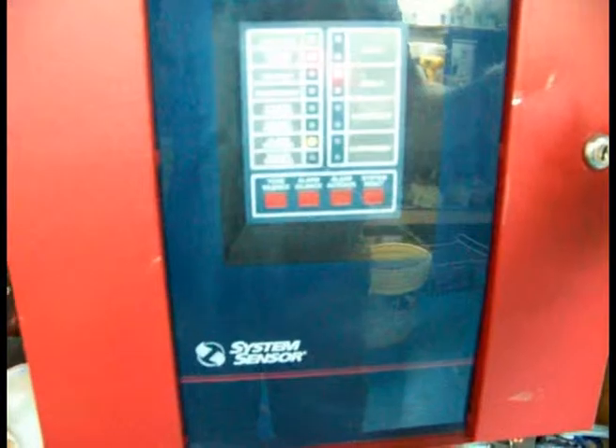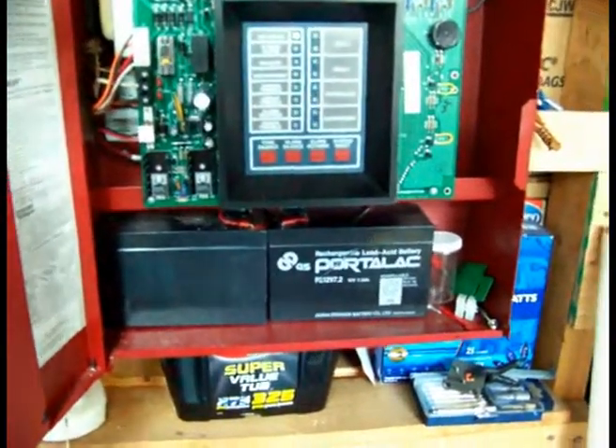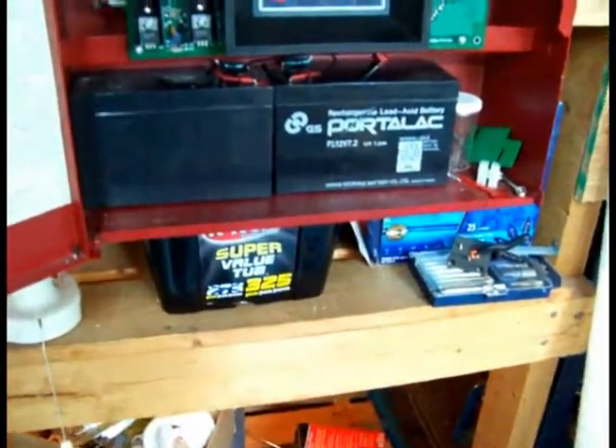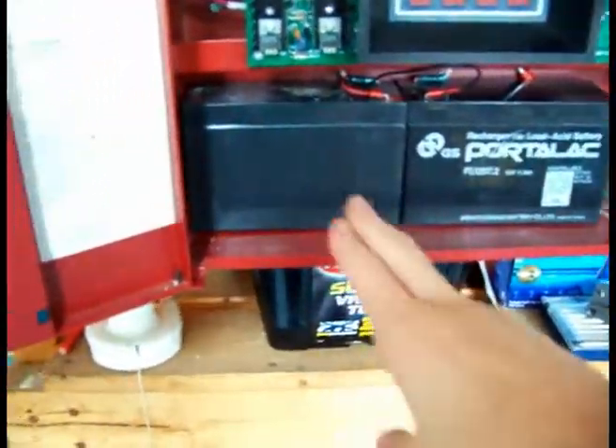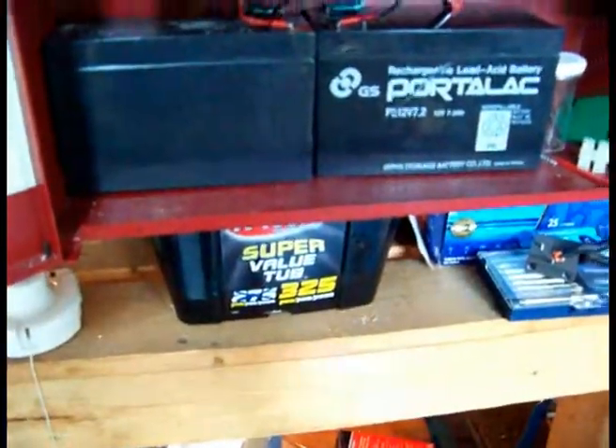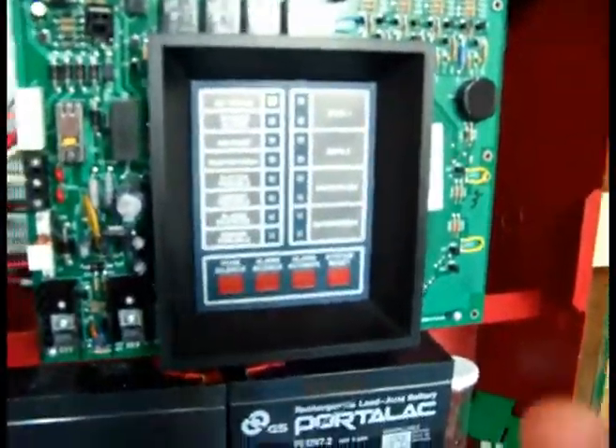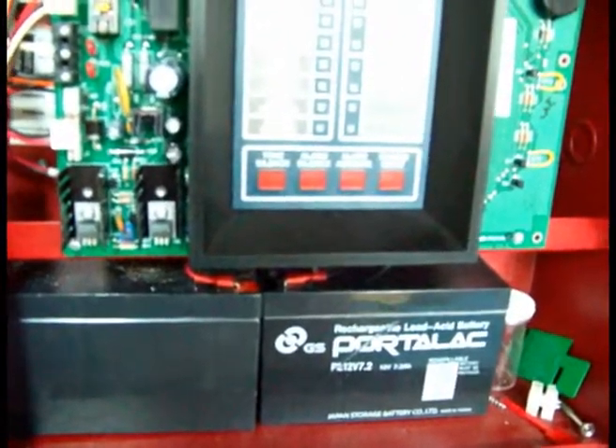Okay. And we're going to reset the panel, of course. This is probably the most interesting system test I've ever done. But I'm just going to tell you one thing — these batteries are actually not so healthy. One battery is pretty good, but the other one is pretty much dead. So it works on the panel because there's probably still some charging currents circulating in the batteries, but they're worn out, so they're not really performing very well.